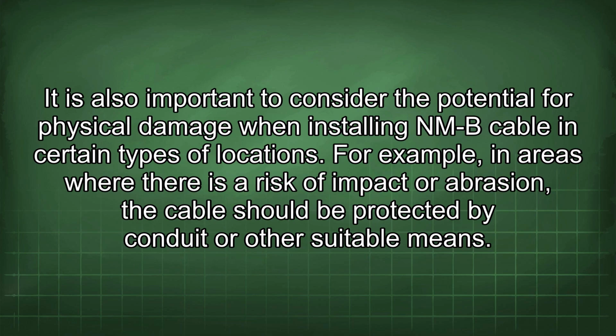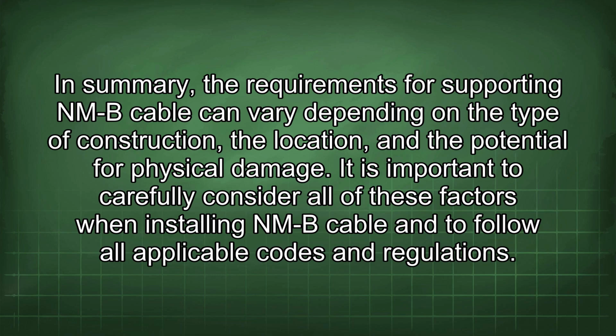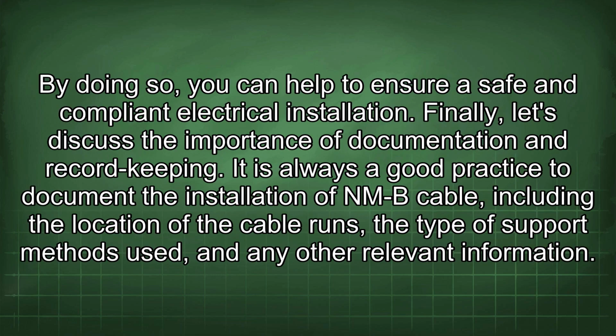It is also important to consider the potential for physical damage when installing NMB cable in certain types of locations. For example, in areas where there is a risk of impact or abrasion, the cable should be protected by conduit or other suitable means. In summary, the requirements for supporting NMB cable can vary depending on the type of construction, the location, and the potential for physical damage. It is important to carefully consider all of these factors when installing NMB cable and to follow all applicable codes and regulations. By doing so, you can help to ensure a safe and compliant electrical installation.